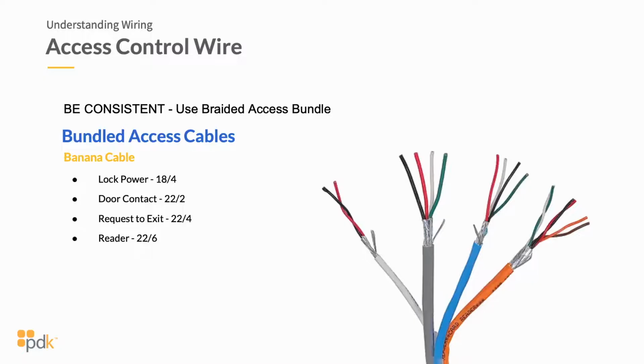So use banana cable. Let me come back to the slide here. You'll see locking power is typically 18/4, door contacts 22/2, request to exit 22/4, and a reader is 22/6. That's typically what's provided to you in the banana cable.